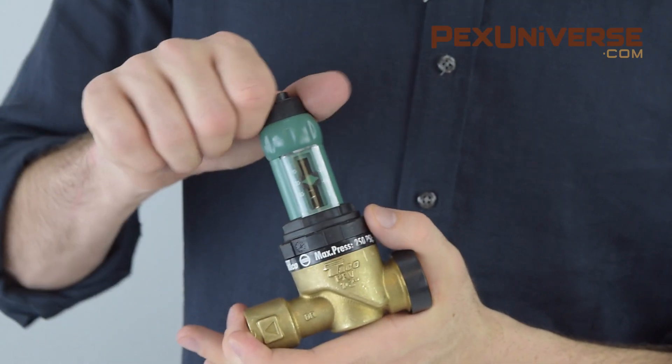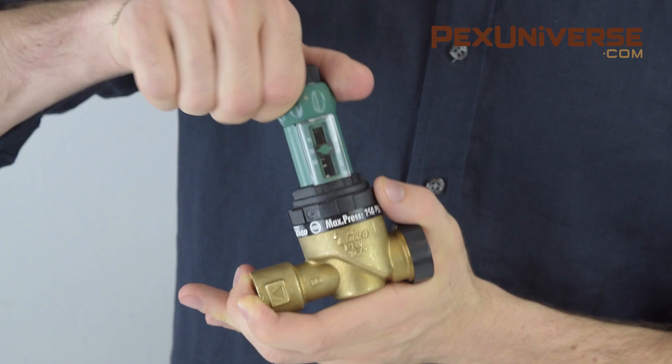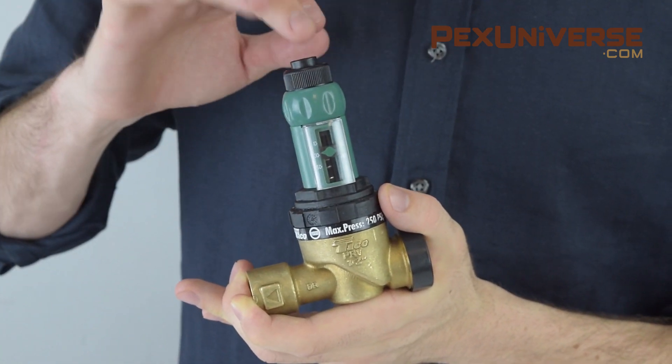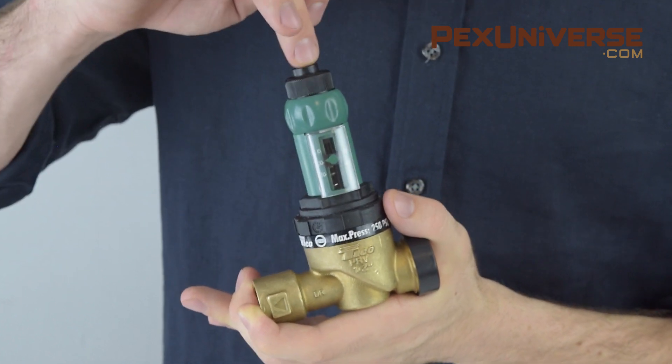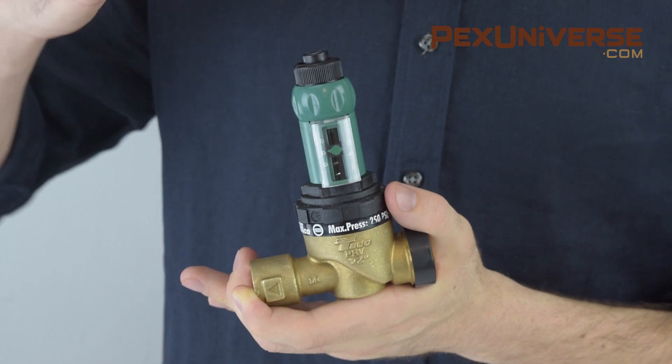This cartridge-style reducing valve from Taco is used in hydronic and radiant heating systems to feed water to the system when pressure drops below a certain level. It's called a pressure reducing valve but works in a different way. To change the pressure range on this product, you loosen the top part and this knob changes the range. There's also a fast fill button to increase flow to the system manually — you simply press it on top of the valve.